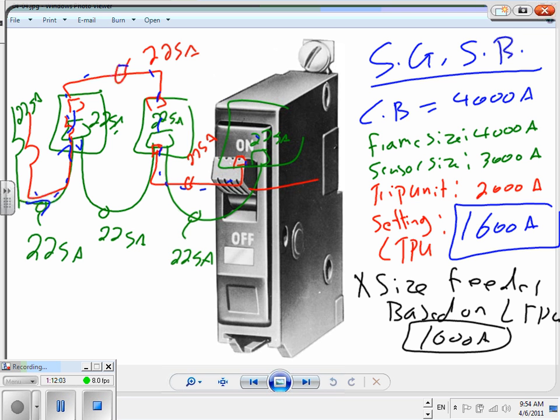Now, I always told you guys to size the standard circuit breakers per 240.4. If you go to 240.4, right underneath the table, I don't know how many of you have paid attention, it says non-adjustable circuit breakers and fuses. The sizes you get, 15, 20, 25, 30, are directly for non-adjustable circuit breakers, right under that table. If it's an adjustable circuit breaker, where are you going to go? To the manufacturer's setting. You are going to be setting these circuit breakers.